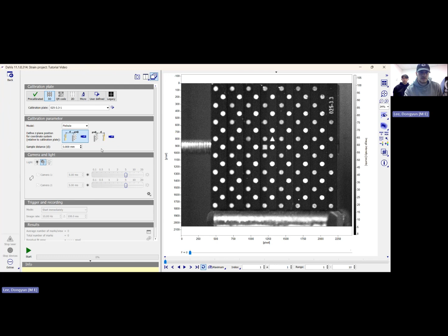You want to make sure it's selected as 3D for the calibration plate. Model is a pinhole. It is 0 distance because we have it set where our sample will be set. So make sure all of that is accurate to where you have your camera. If you have it behind where your sample would normally be, make sure you choose that selection. In this case, we have it where ours is, so it's set to 0. Please make sure to choose calibration plates. For us, we have 3.3 as our calibration plate. So select this number and hit the start button. And now the software is doing the calibration.